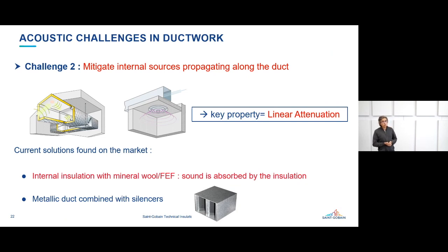The second challenge you have to address with ductwork is being able to mitigate internal sources propagating along the duct. The key rating for this issue will be the linear attenuation property, which we can measure. And the current solutions you can find on the market are twofold. The first one, which is quite common, is to consider internal insulation based on open cell material, such as mineral wool or flexible elastomeric foam from our colleagues at Kaimann, for example.